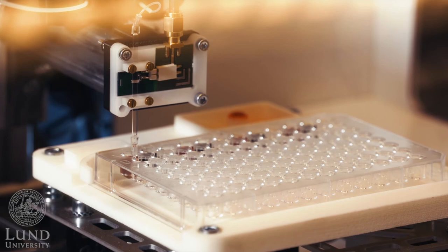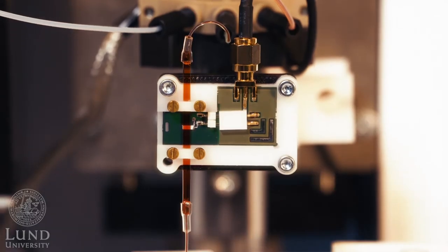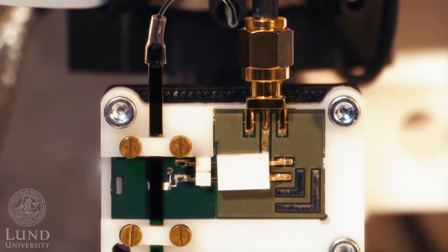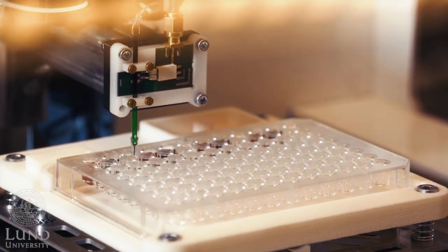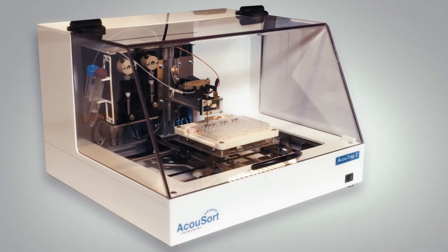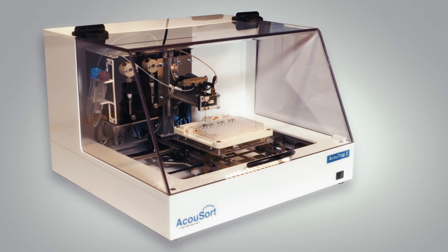In the AcouTrap platform, the acoustic trap is mounted as the tip of a pipetting robot, where samples and reagents are pulled up from and released into 96 well plates. This enables automation of various cell and subcellular particle assays.